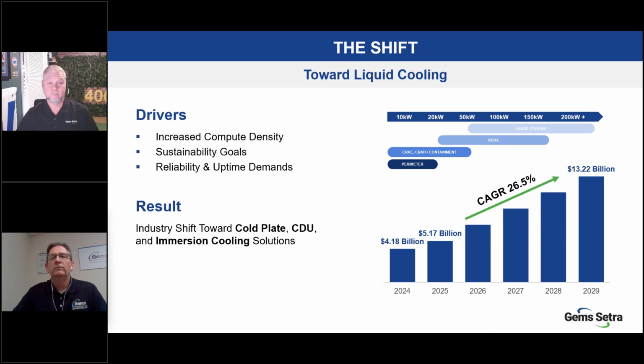a necessity. Other factors driving liquid cooling are sustainability and uptime, and liquid cooling is far more efficient than air cooling methods, helping reach sustainability goals. Liquid cooling also helps to lower PUE, or power use effectiveness. That's a metric followed by data center professionals, and the goal is to get that number as close to 1 as possible. And liquid cooling has provided far lower PUE than traditional air. We also want to note that the rate at which AI and high-performance computing is growing is resulting in unprecedented growth rate in this market. You see the compound annual growth rate listed there of 26.5%. Depending on the publication, we've seen anything from 18 to 30%. But regardless of that exact number, liquid cooling's future dominance is evident here.